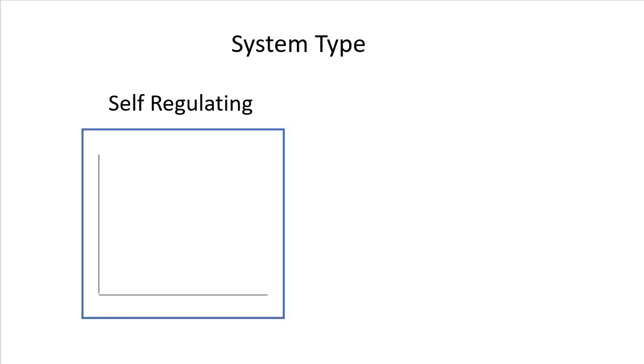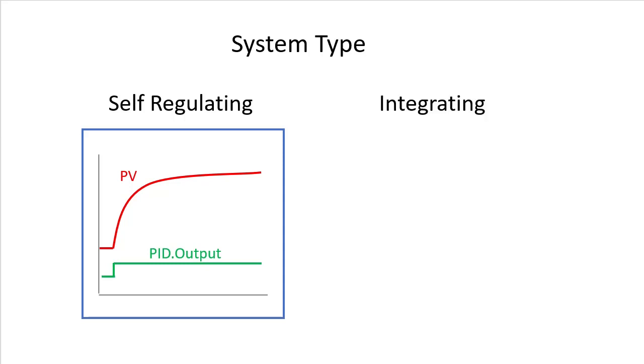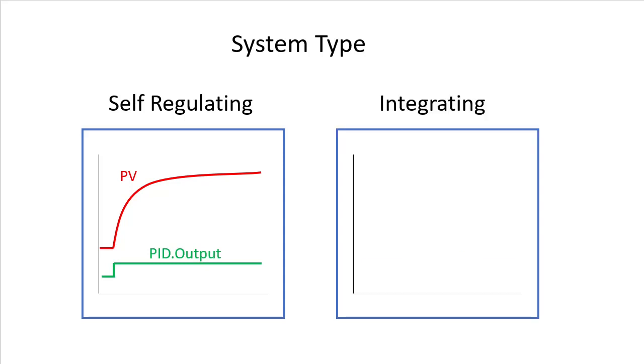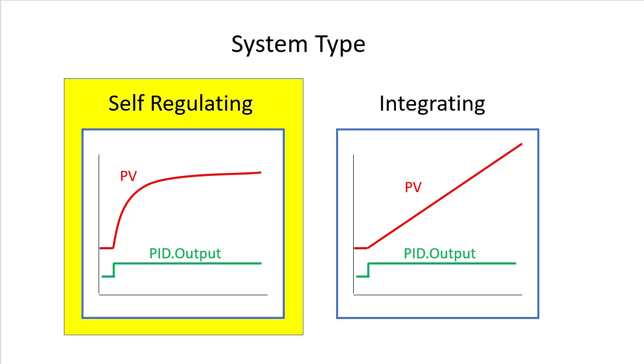And finally, we need to know what type of system we have. Do we have a self-regulating system? That is, a system that when given a change in the PID output, it levels off after a while. Or an integrating system – one that just keeps going up. We know from the previous videos that our system acts like this so we have a self-regulating system.